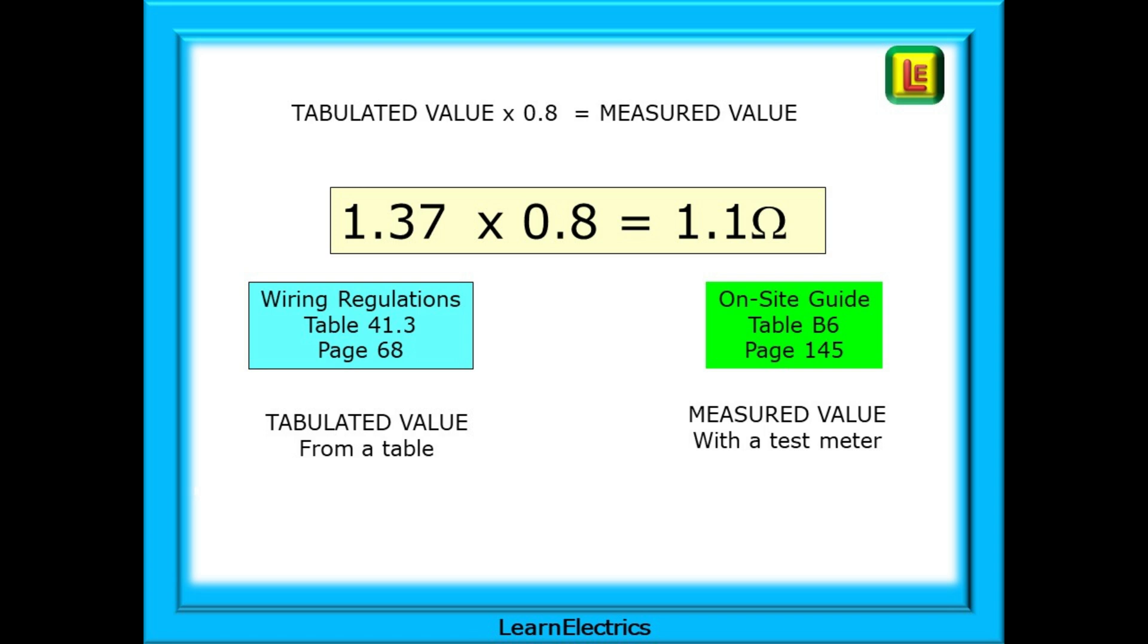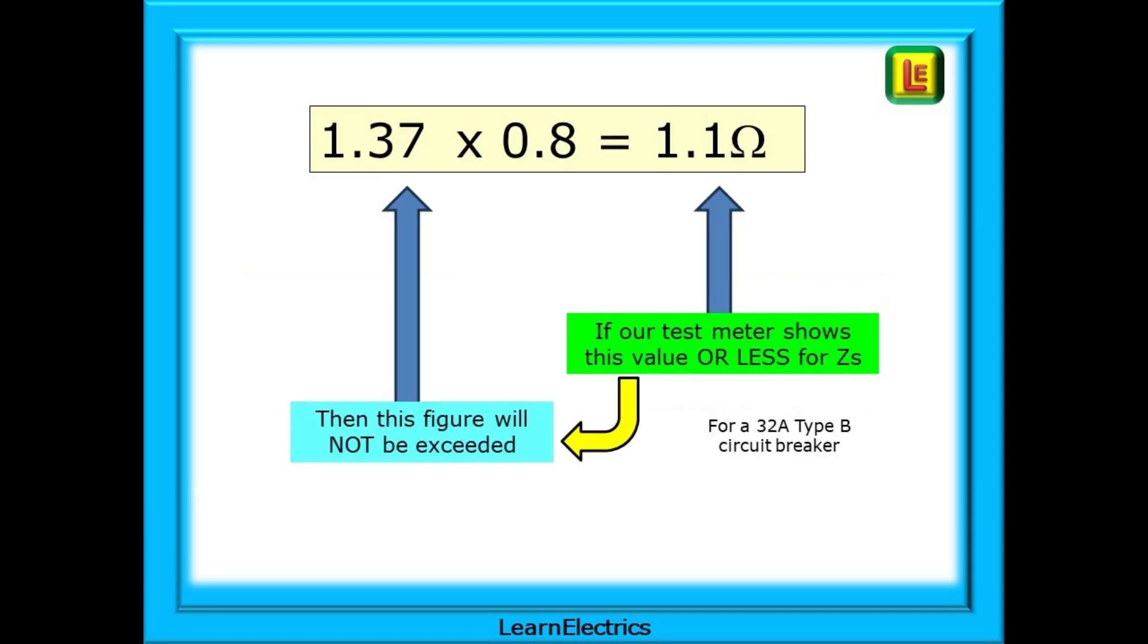1.37 multiplied by 0.8 equals 1.1 ohms. This 1.1 ohms is called a measured value. It's the ZS that we will measure with our test meters when on site. We've taken the tabulated value from a table in the wiring regs multiplied by 0.8 and arrived at our measured value. What this means is that for the 32 amp type B breaker if our test meter shows 1.1 ohms or less for ZS then 1.37 ohms is not going to be exceeded at 70 degrees Celsius.